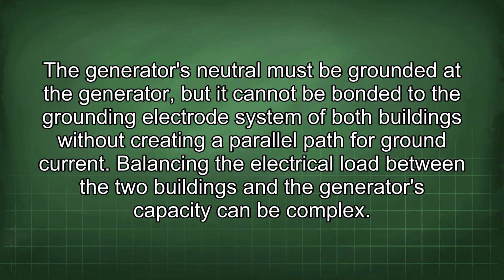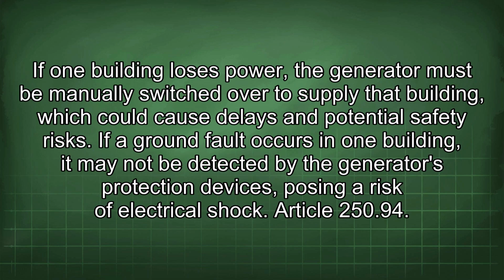Balancing the electrical load between the two buildings and the generator's capacity can be complex. If one building loses power, the generator must be manually switched over to supply that building, which could cause delays and potential safety risks. If a ground fault occurs in one building, it may not be detected by the generator's protection devices, posing a risk of electrical shock.